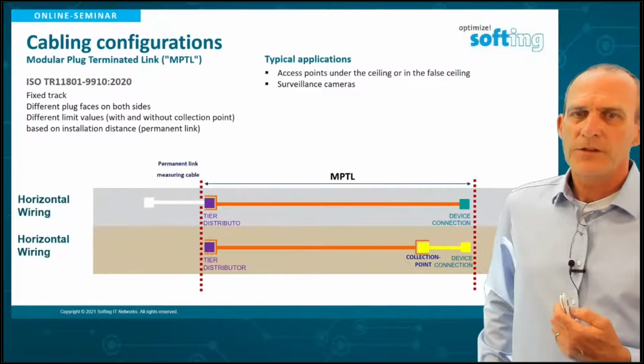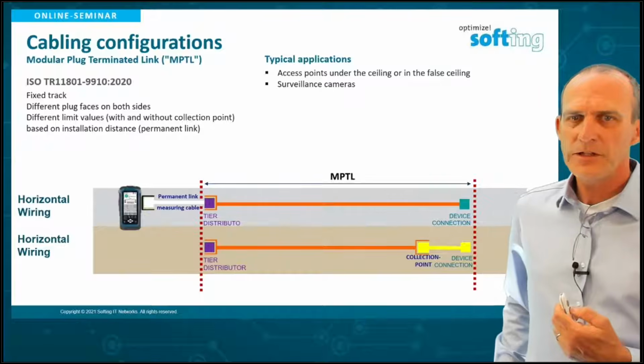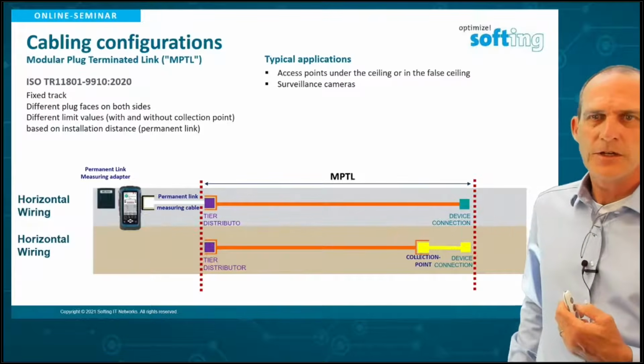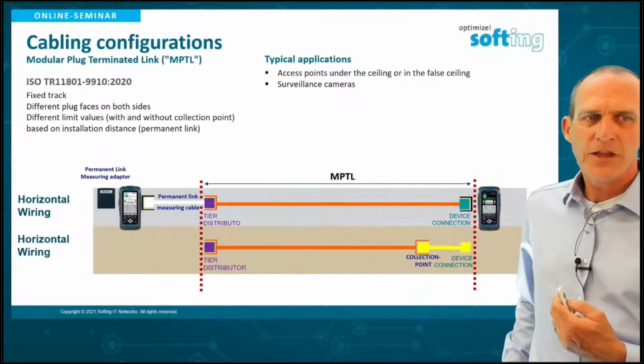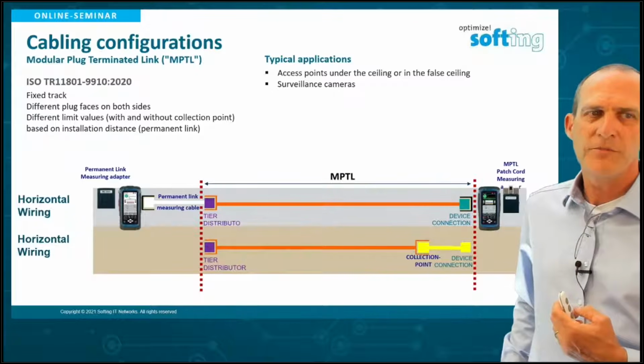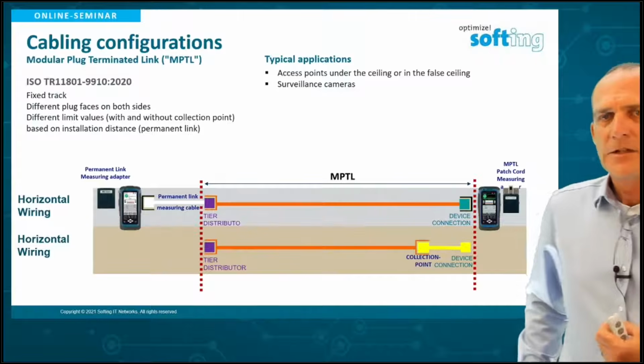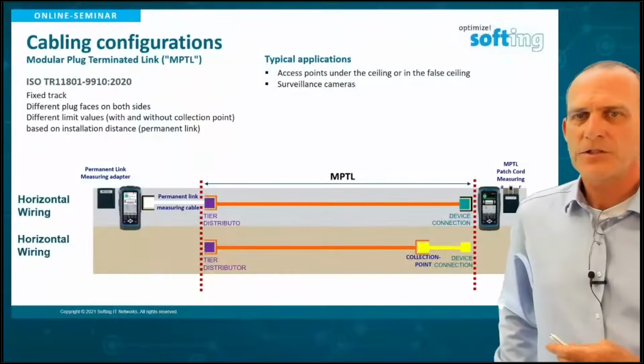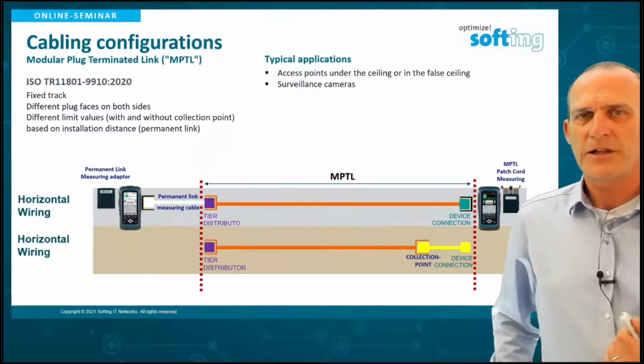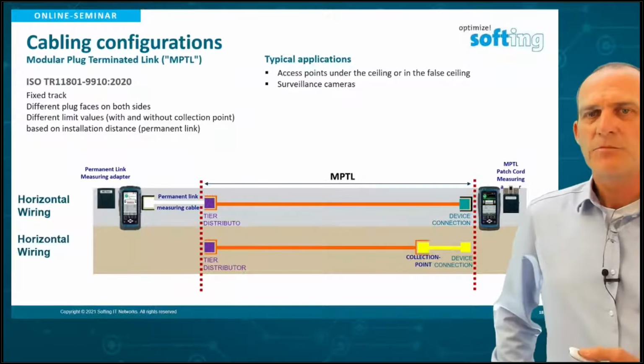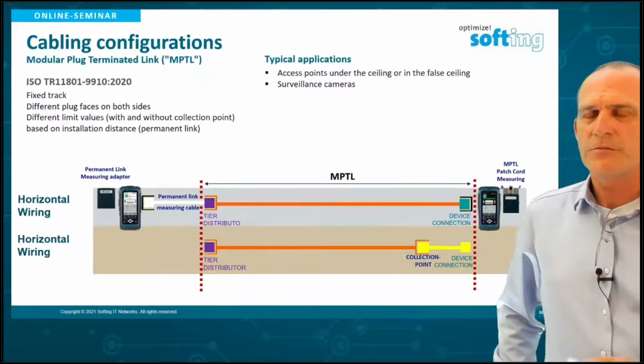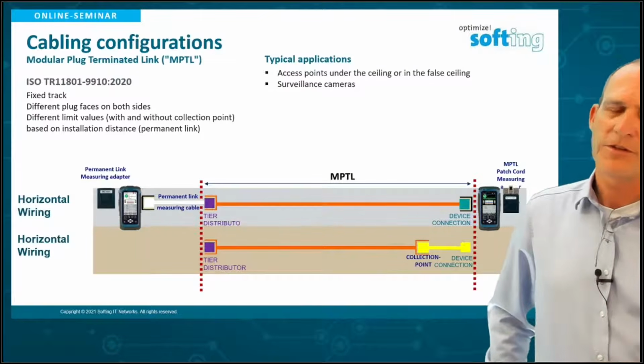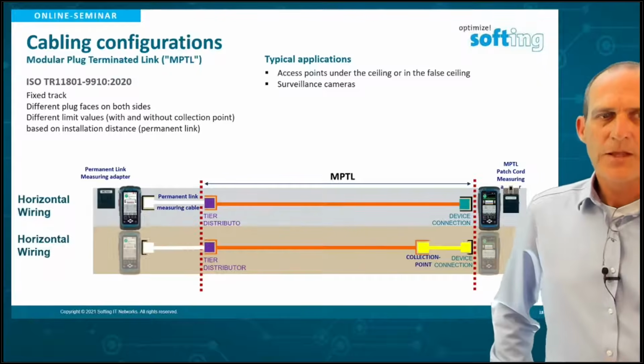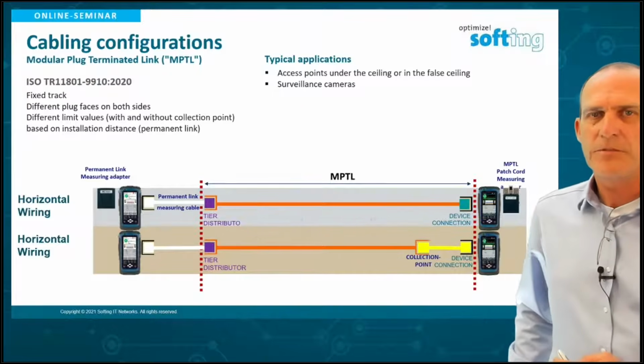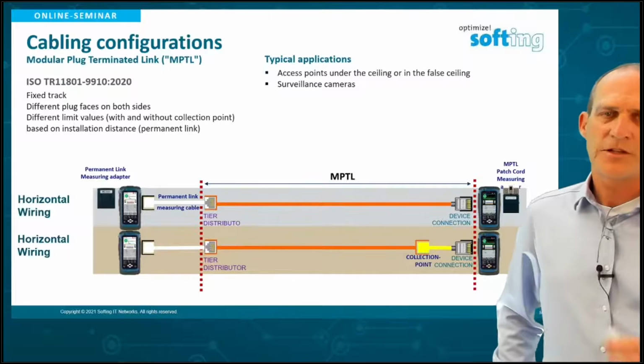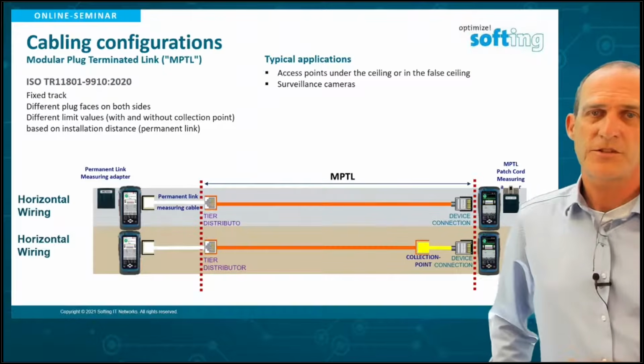We do that with, on one side, a permanent link measurement cable and a permanent link adapter, and on the other side of the link, a patch cord or MPTL measurement adapter. For us it's the same thing, because the patch cord adapters and MPTL adapters are basically the same, but for ease of use we have two different versions, calling one patch cord, the other MPTL. That's how they are tested. Important here is you cannot use channel adapters, because they mask out the first and last connector.